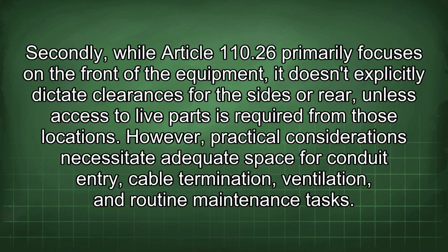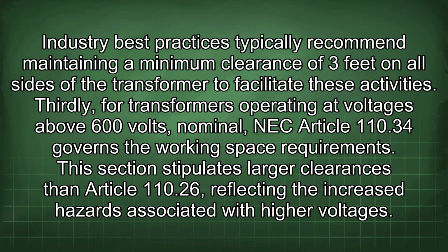Secondly, while Article 110.26 primarily focuses on the front of the equipment, it doesn't explicitly dictate clearances for the side or rear, unless access to live parts is required from those locations. However, practical considerations necessitate adequate space for conduit entry, cable termination, ventilation, and routine maintenance tasks. Industry best practices typically recommend maintaining a minimum clearance of 3 feet on all sides of the transformer to facilitate these activities.